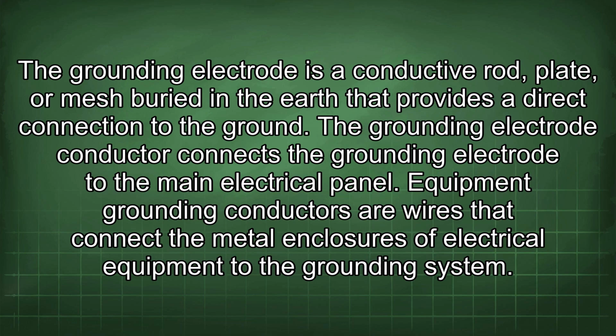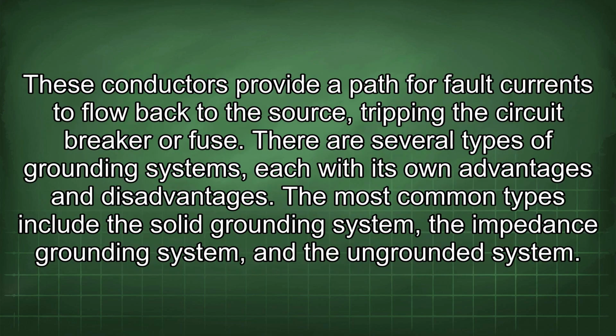Equipment grounding conductors are wires that connect the metal enclosures of electrical equipment to the grounding system. These conductors provide a path for fault currents to flow back to the source, tripping the circuit breaker or fuse. There are several types of grounding systems, each with its own advantages and disadvantages. The most common types include the solid grounding system, the impedance grounding system, and the ungrounded system.